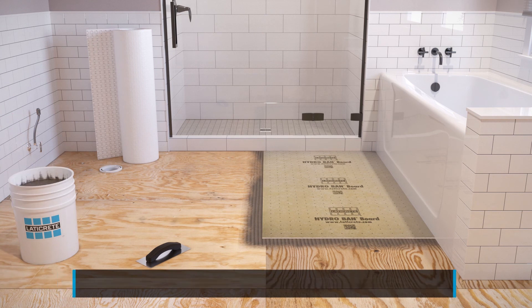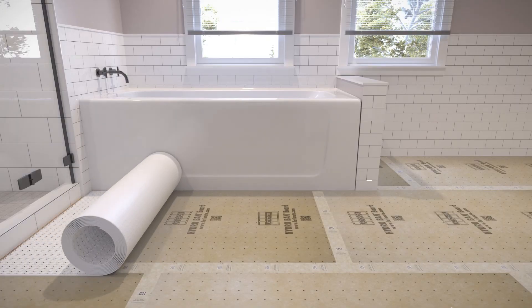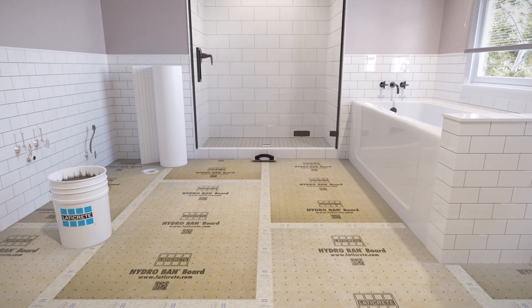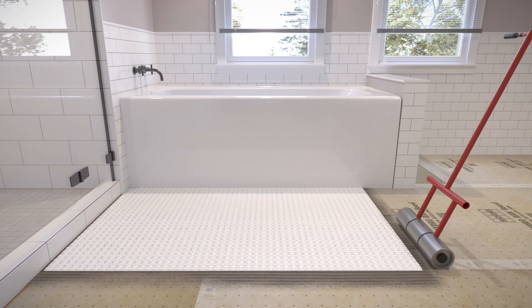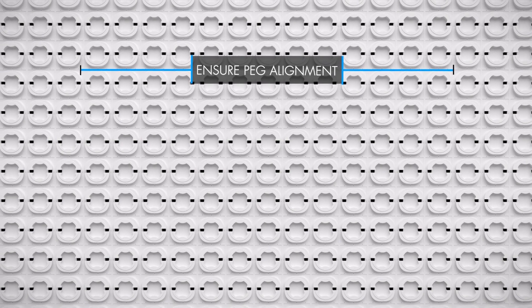The benefit of the HYDRO BAN Board is best seen when installing the system over concrete. Prior to laying any thinset, measure and cut a length of StrataHeat mat to suit your room using a utility knife and/or scissors. Once the mat is cut to size, apply a layer of thinset with a quarter inch by quarter inch square notched trowel. Position the StrataHeat mat fleece side down into the adhesive bed and embed it using a float roller, removing any air pockets. Be sure to tightly lay additional sheets in parallel to ensure that the pegs are aligned.